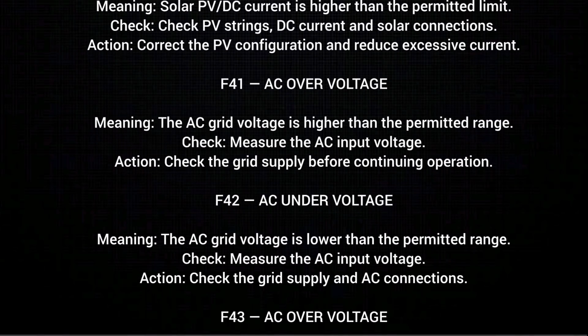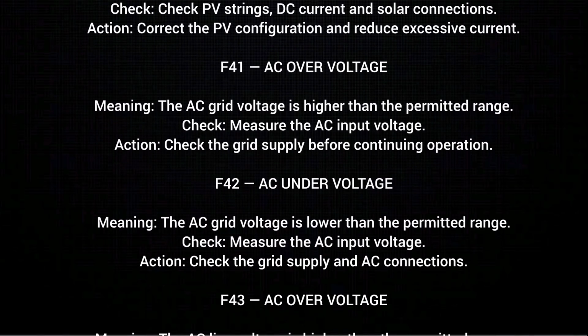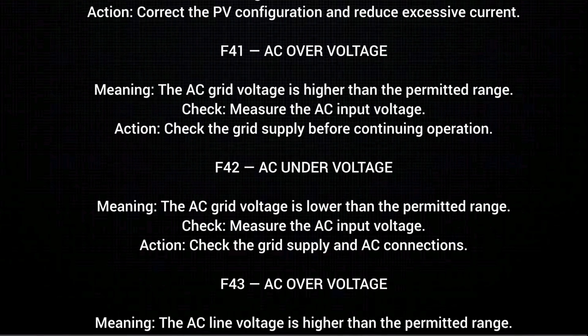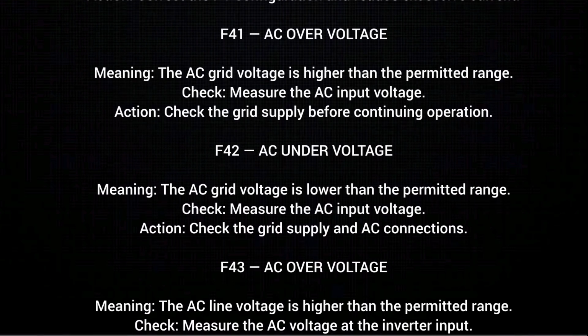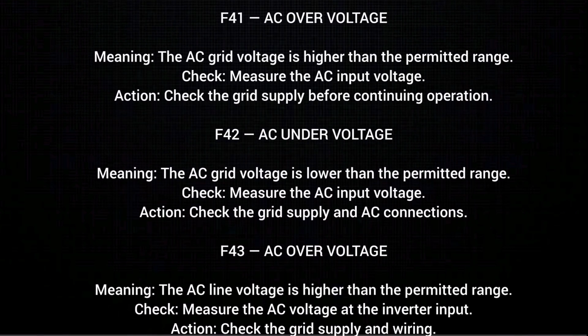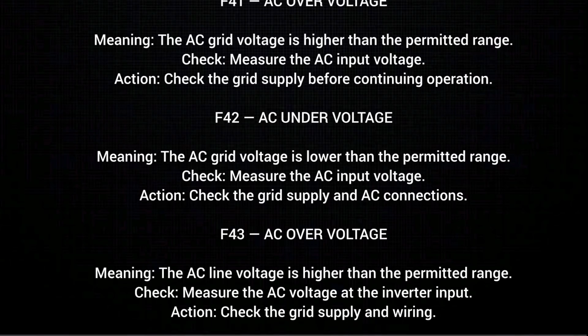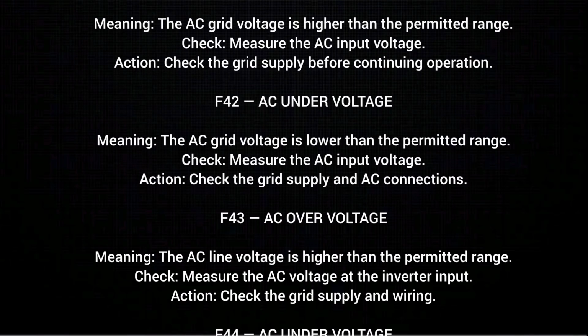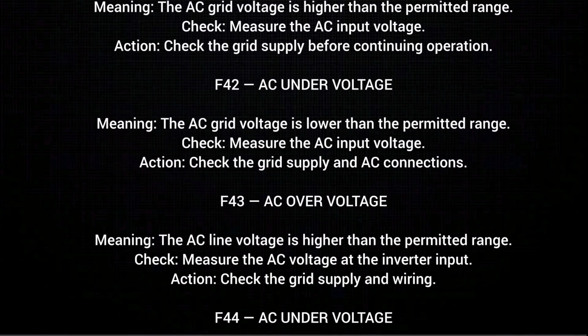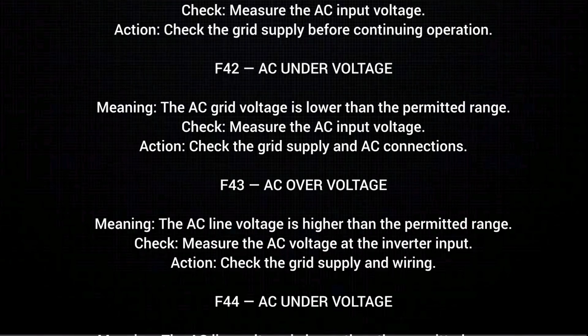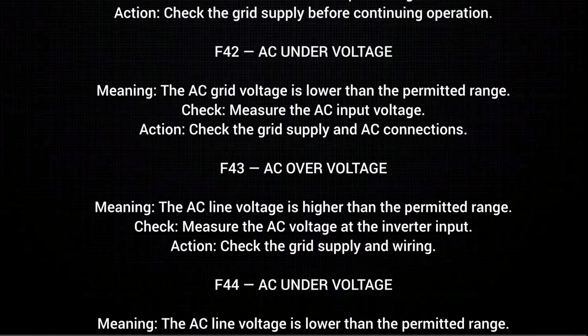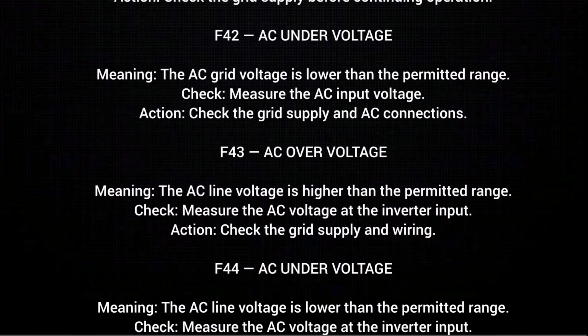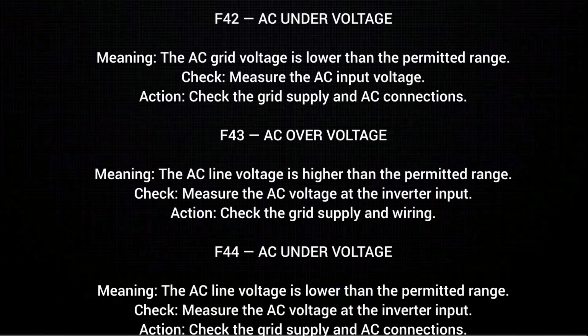F42. AC under voltage, meaning the AC grid voltage is lower than the permitted range. Check. Measure the AC input voltage. Action. Check the grid supply and AC connection. F43. AC over voltage, meaning the AC line voltage is higher than the permitted range. Check. Measure the AC voltage at the inverter input. Action. Check the grid supply and wiring.